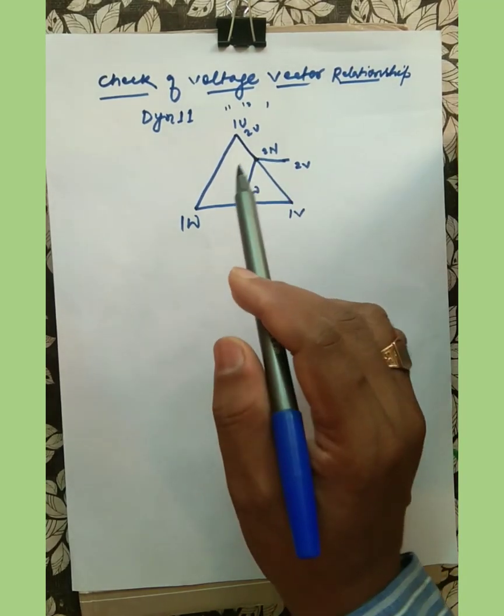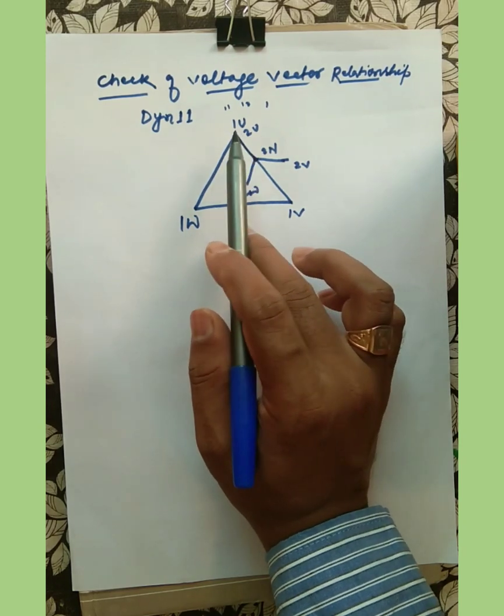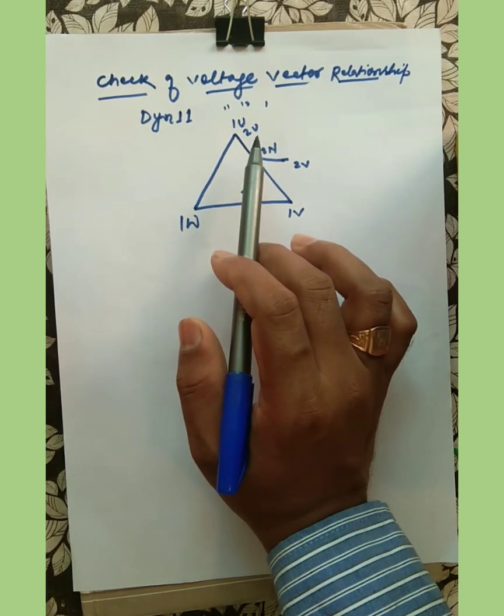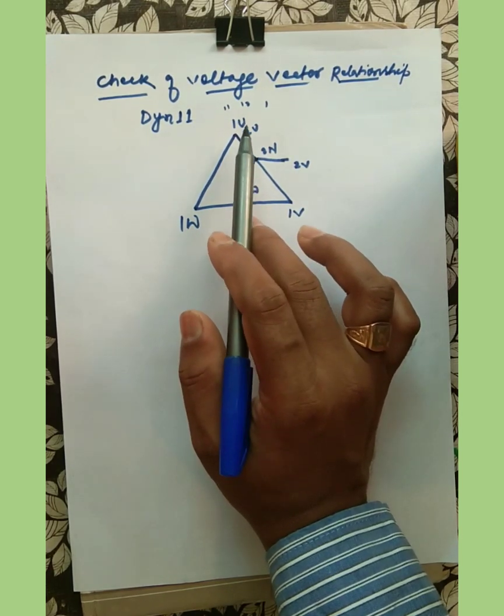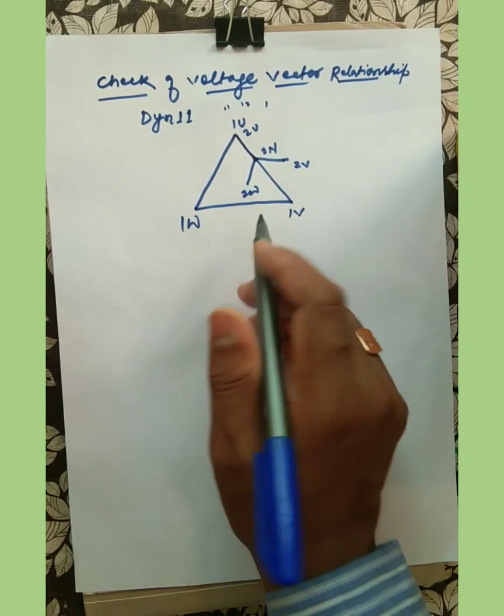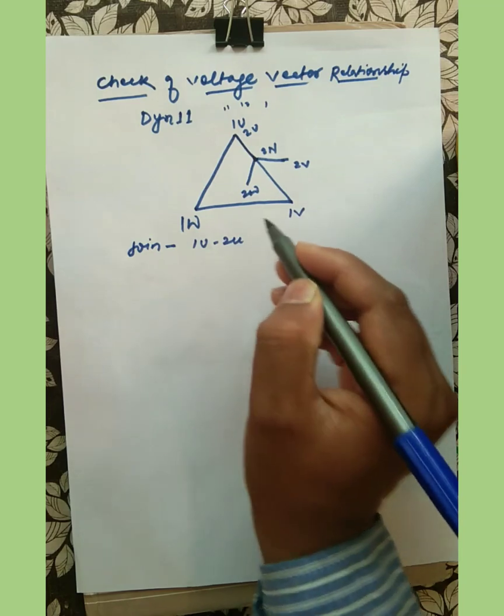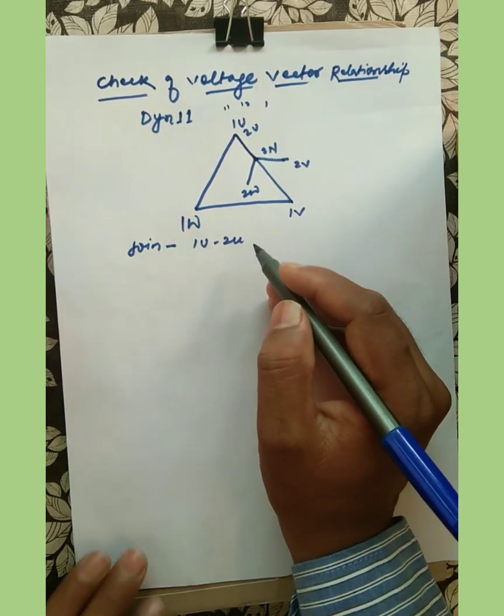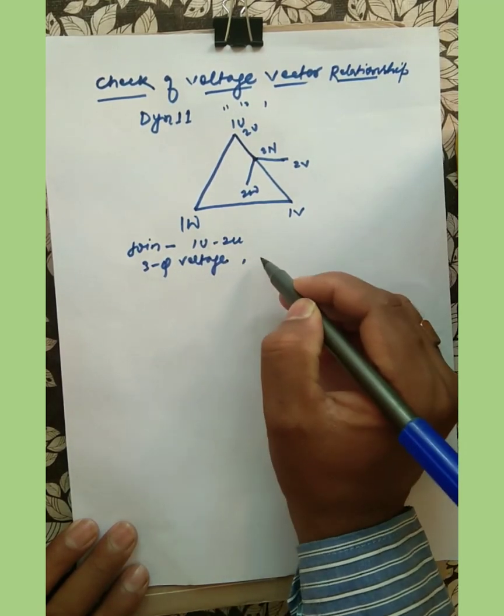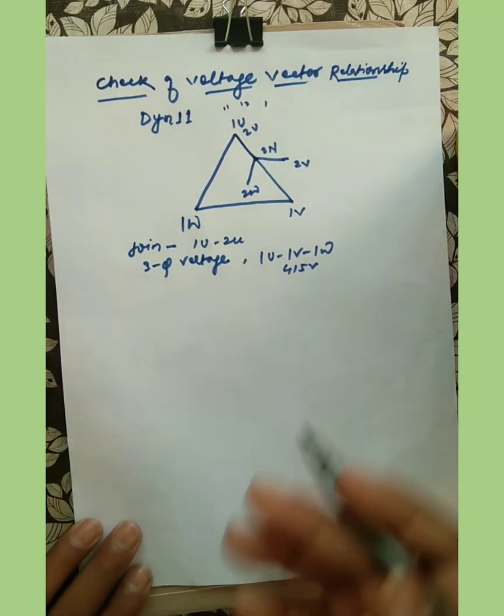In this vector relationship, 1U and 2U are connected. If we connect 1U and 2U, that means the U phase of primary and U phase of secondary — you can say R phase primary and R phase secondary — are joined. We join 1U and 2U and we apply a three-phase voltage to the primary, that means 415 volts to 1U, 1V, and 1W.